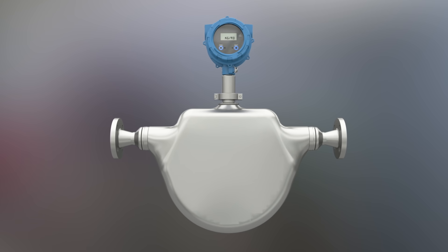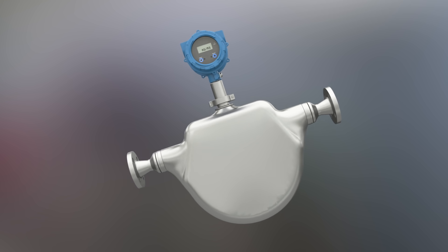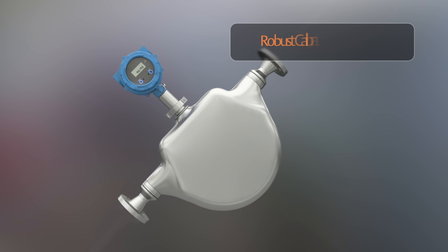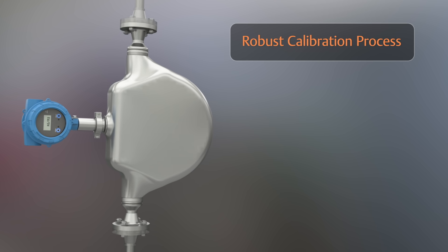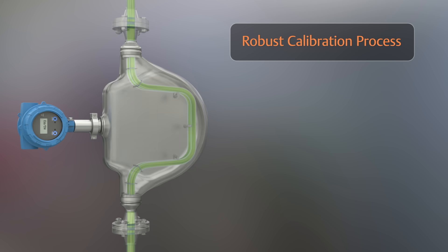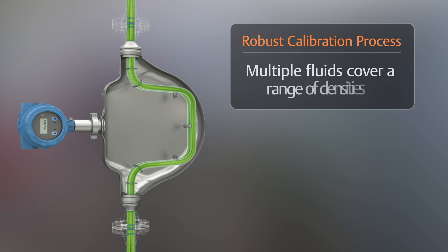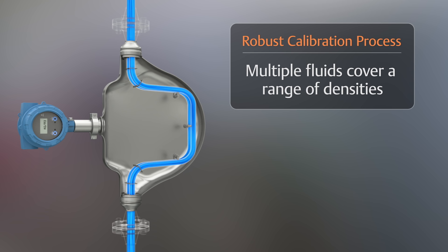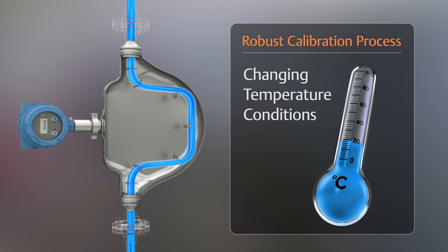Let's look at how this is measured using a robust accredited calibration process. The Compact Density Meter is calibrated using multiple fluids to cover a range of densities and to ensure a linear response. The meter is also calibrated for temperature, starting at room temperature and then at elevated temperatures.